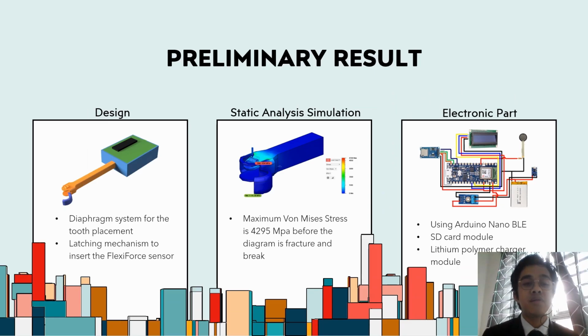For the preliminary results of the proposal, I have come up with a design, a static analysis simulation, and the electronic parts needed for the system. For the design, a diaphragm system is used as a tooth placement as it can bend without breaking, with a latching mechanism for the mouthpiece to insert the FlexiForce sensor. For the static analysis simulation, the diaphragm is under 450 Newton force, which is standard for human bite force, and based on the simulation, the maximum von Mises stress to break the diaphragm is 4295 megapascal, so a lot of force is needed to break the diaphragm.